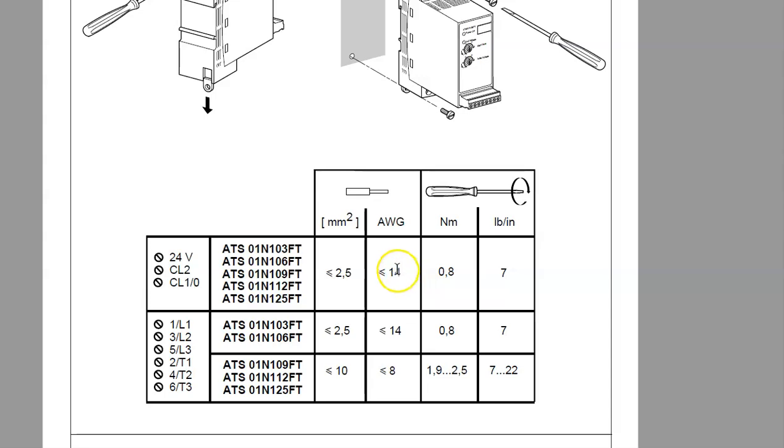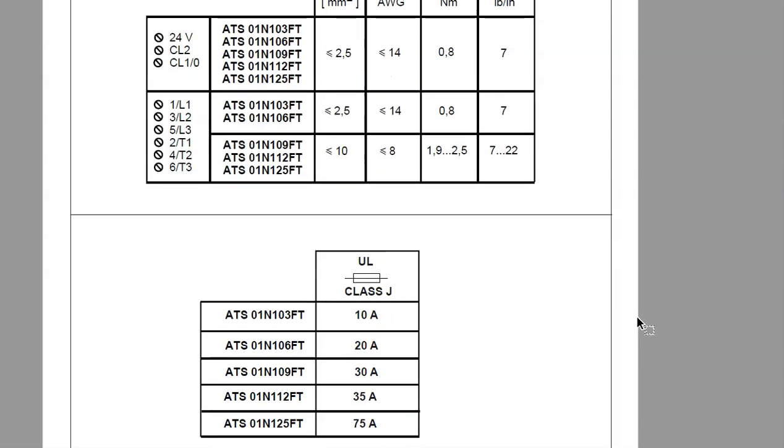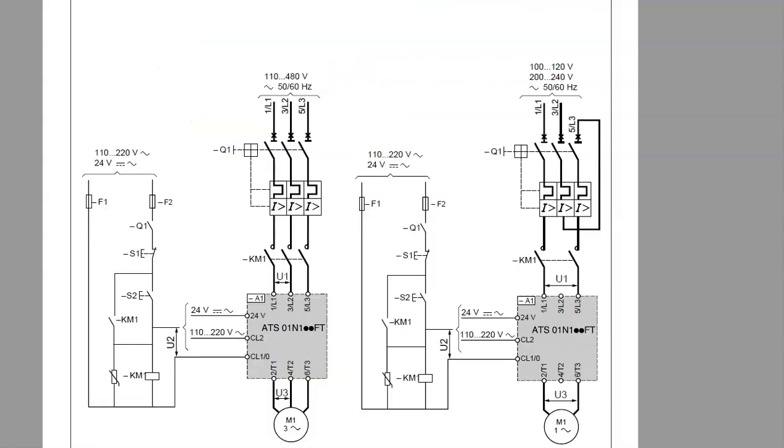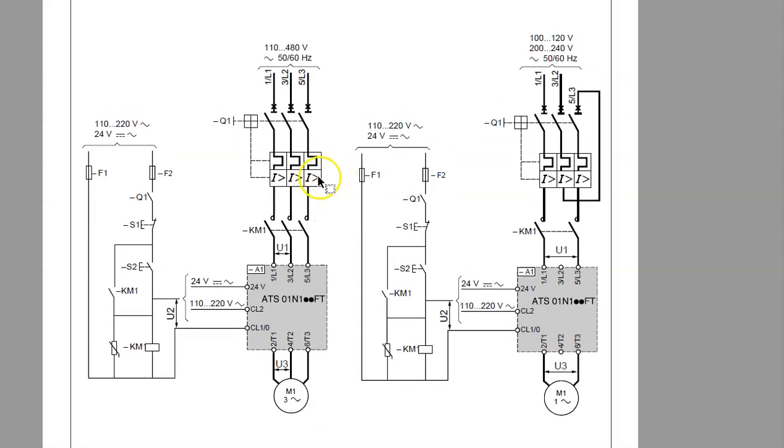There's a chart covering all the screws, the torque values allowed, and the wire gauge that can be inserted — AWG 14 and smaller up to a number 8 on others — with torques given in inch-pounds or newton meters. It also covers the types of fusing and maximum fuse sizes, including Class J fuses which relate to speed of operation. This is going to be a somewhat unfamiliar layout because it's a European standardized diagram rather than North American standard.